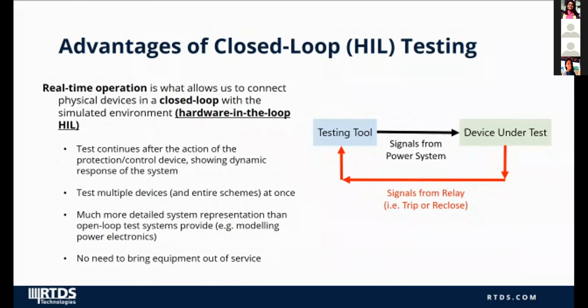The principal advantage of running in real time is the ability to connect external hardware in a closed loop with the simulated environment. This means not only observing the response of the device to an imposed signal, but also interfacing the device's response back into the simulated network. This is what we call hardware-in-the-loop simulation. It's only possible if we are updating the inputs and outputs of the simulation continuously in real time.